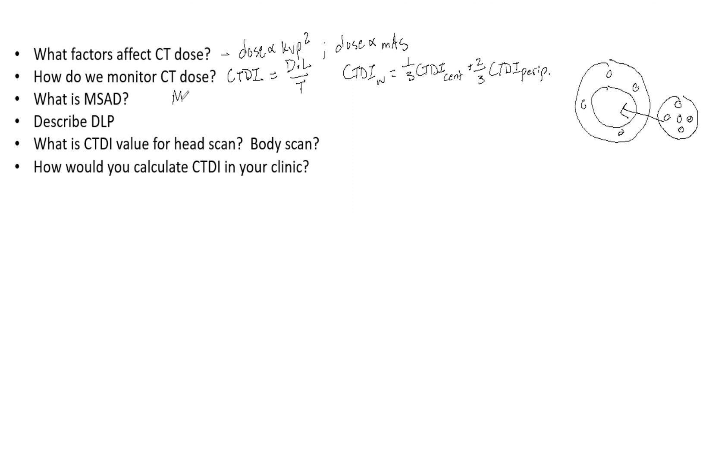Now MSAD, how I'm going to write it here, is equal to the CTDI weighted, so that's CTDIW, divided by the pitch of the CT table. So that is over infinite length. And sometimes this is also called CTDIVOL, and that stands for volume.